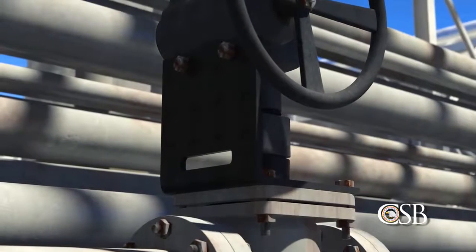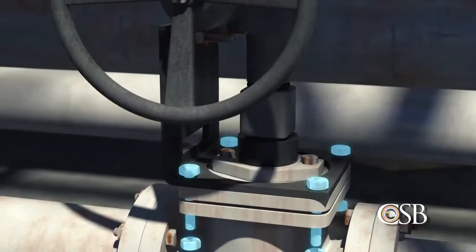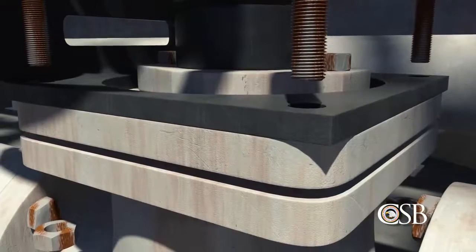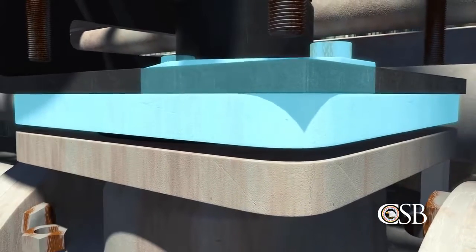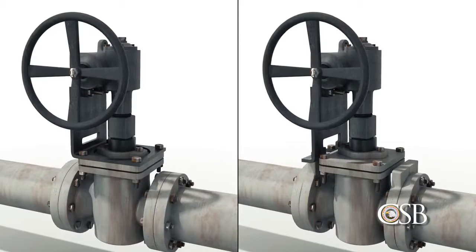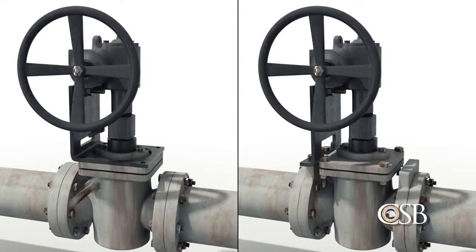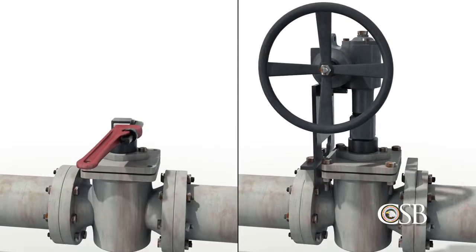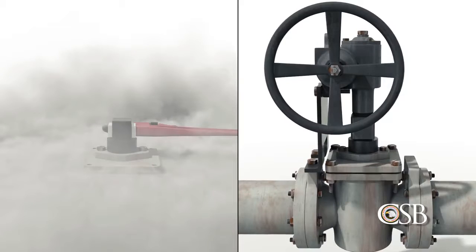The gearbox was connected to the valve body by the support bracket using bolts. The operators removed 4 vertical bolts from the valve. But unknown to the operators, these bolts also secured a critical pressure-containing component of the valve known as the top cap. Approximately 3% of the numerous plug valves in the refinery's alkylation unit were designed so that the gearbox support bracket attached to the top cap. With this 30-plus-year-old design, removal of the gearbox support bracket can have catastrophic consequences.